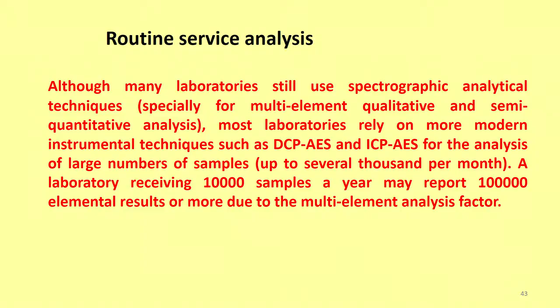For routine service analysis, although we normally follow both multi-element and sequential approaches, the more modern instrumental techniques are direct current plasma AES and ICP-AES for the analysis of a large number of samples. For multi-element analysis, DCP-AES is much better, and there are reports that a laboratory receiving about 10,000 samples per year may report 100,000 elemental analyses or more due to the multi-element analysis factor alone. So, it is a very powerful technique, especially if the requirement of metal analysis is continuous and regular. It is much faster than atomic absorption also, because even though multi-element analysis is now possible with atomic absorption, it has not reached the same efficiency as ICP-AES.